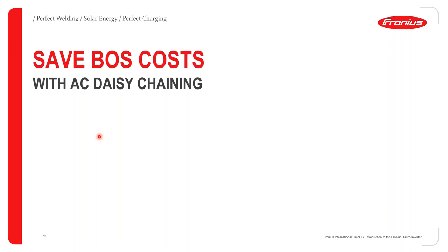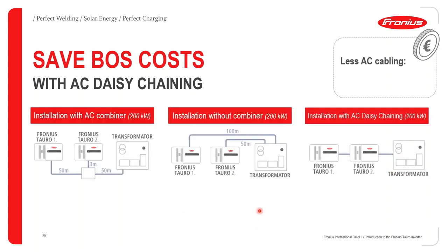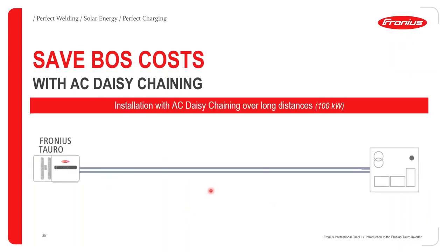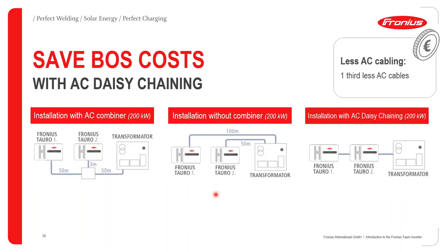So let's now look at and compare different scenarios that you can encounter in the field. These scenarios are looking at an installation of up to 200 kilowatt on the PV side, and therefore that means you would require a minimum of 2 inverters, maybe 100 kilowatt Tauro. So we have one consideration, or one comparison, that is with an AC combiner box.